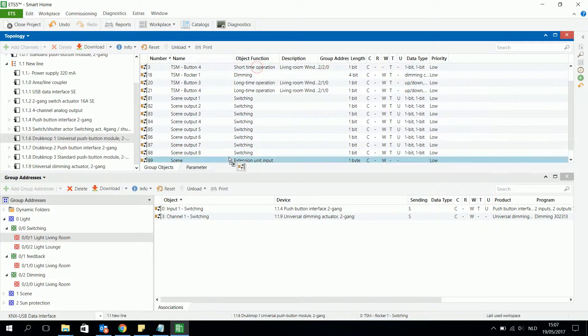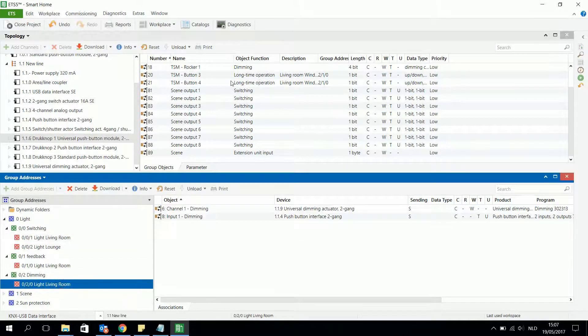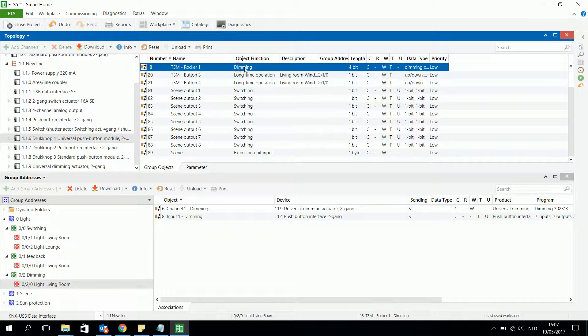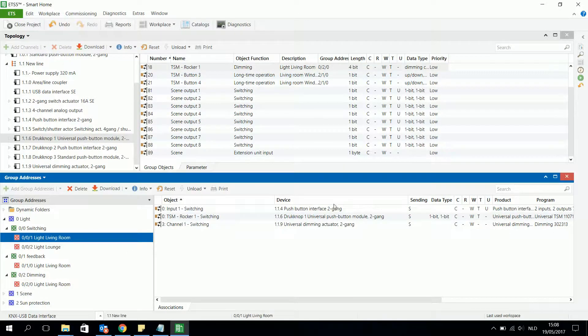I connect the switching object of rocker 1 to the switching group address, and associate the dimming object with the dimming group address. With input 1 I can make the light darker and brighter, while with rocker 1 — buttons 1 and 2 — button 1 makes it brighter and button 2 makes it darker. I can switch on and off with input 1 of device 1.1.4, and with rocker 1 I can switch the light on with the left button and off with the right button. This is how to program dimming for a light.